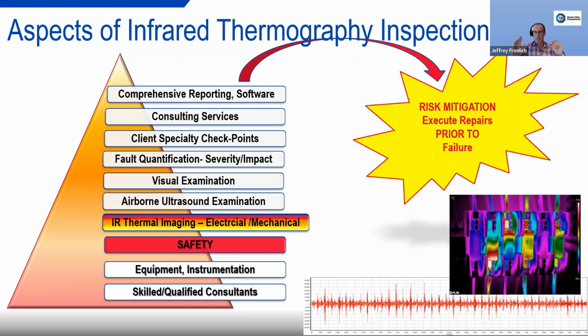So you're going to count on Steve and the team and the arc flash professionals to provide good safety labels, and that will give us our PPE categories and levels. Of course, with the thermal imaging, the work scope is going to be both electrical and mechanical. Our airborne ultrasound is going to be used on strategic high and medium voltage, as well as low voltage assets, where perhaps it's unsafe due to danger levels, and we can't get a particular cover open. And the use of acoustic airborne ultrasound and/or structure borne will be able to listen inside the asset for anomalies indicative of a wide range of things from mechanical to electrical, corona, arcing, tracking, and things of that nature.